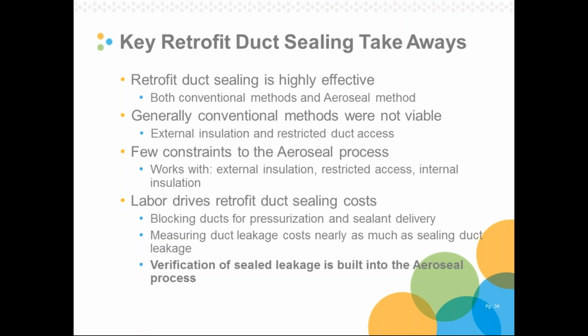The other thing we learned is that whether we're using conventional methods or the Aeroseal method, the labor to prepare ductwork is really the driver of the costs. Blocking ducts for pressurization and sealant delivery is time consuming. There's just no way to get around it. I mentioned earlier that static pressure testing, you have to do these things too, and that's why that is expensive. When we compare static pressure testing with Aeroseal sealing, we find that there's actually little difference in the amount of time, and consequently not that much difference in the cost. And on top of that, Aeroseal incorporates the testing, and so it has this built-in method for verifying seal leakage, which is a major advantage.